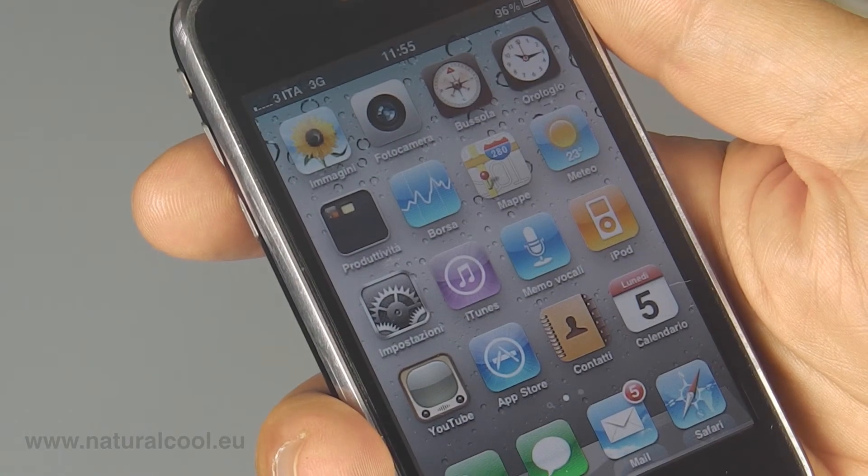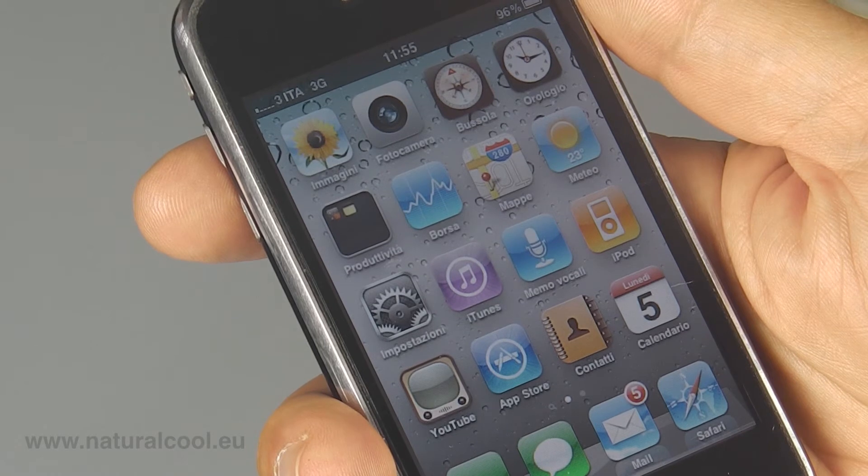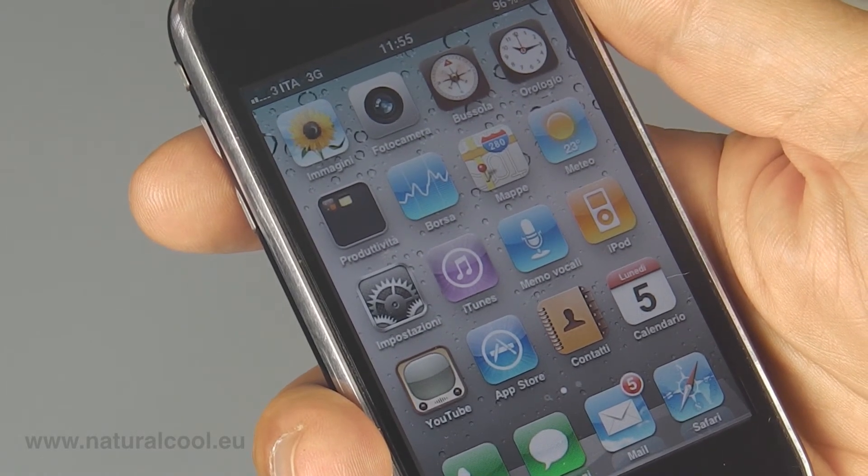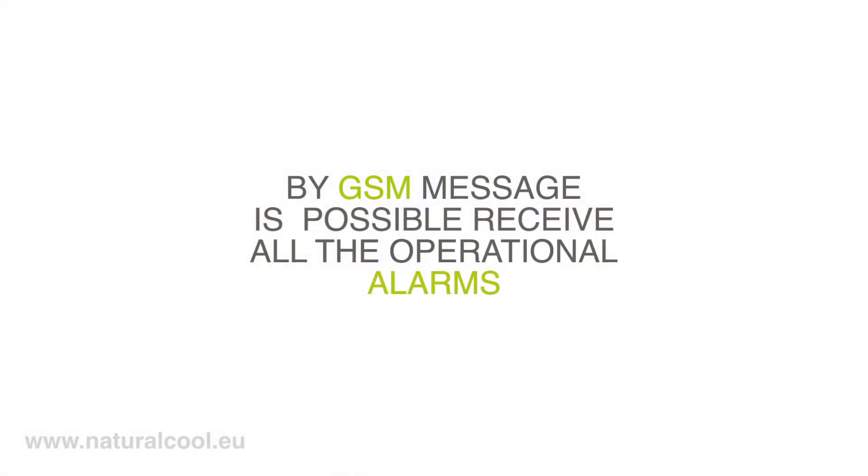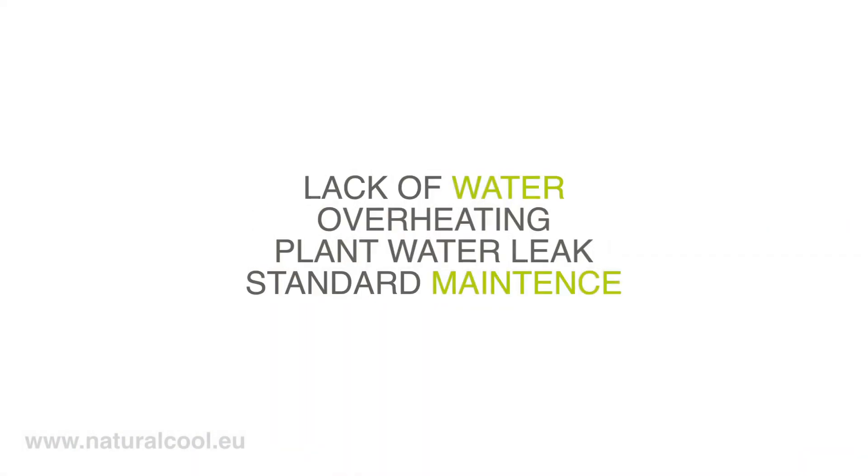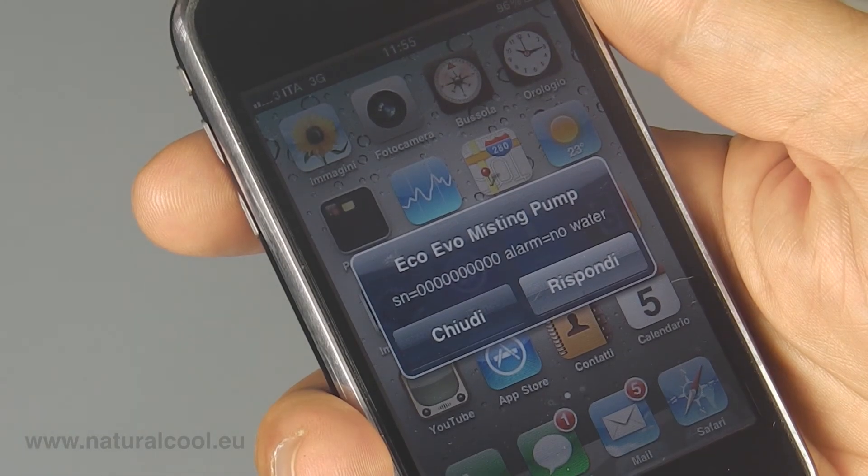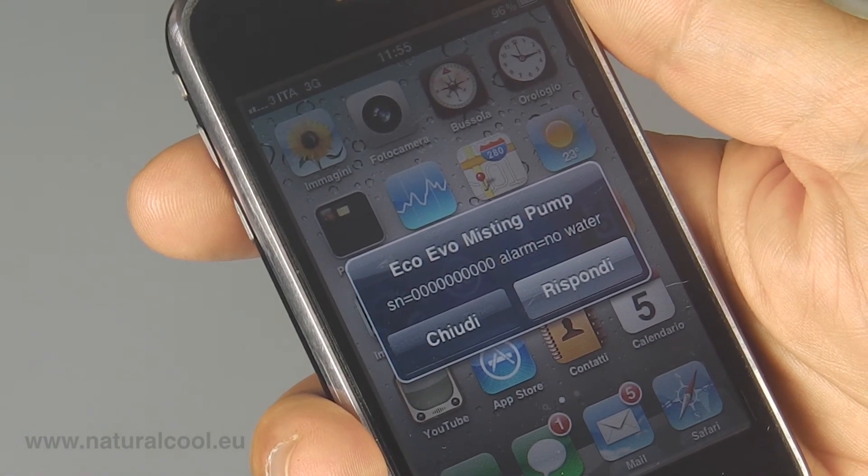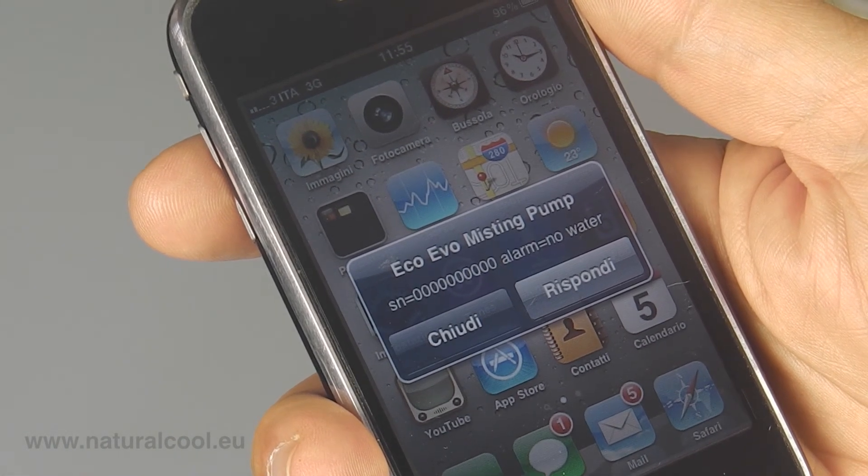Through a simple GSM message addressed to the SIM card inserted in the atomizing unit, it is possible to receive all the operational alarms, such as lack of water, overheating, plant water leak, and notification of the various programmed maintenance operations, in order to promptly know of a possible fault and quickly fix it.